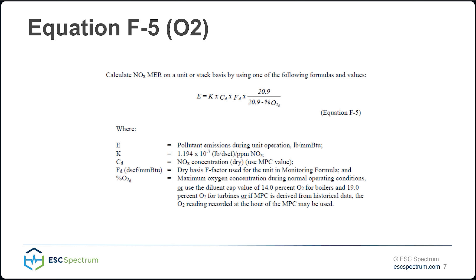In the monitoring plan instructions, it's very clear how to calculate this. If you're calculating NOx MER and your diluent is O2, this is the formula you will use — equation F5, which is identical to equation 19.1. I had a pre-question about what's the best diluent to use so that you're not using the highest number possible for missing data substitution. That's definitely dependent on site operation and equipment. You can have a conversation with the technicians about that if there's something you're wanting to change.